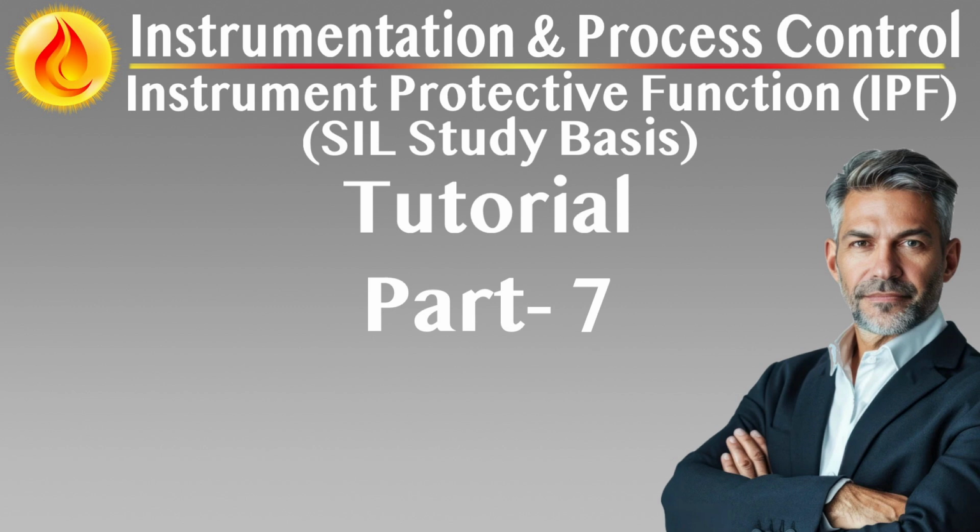Testing, validation, and maintenance requirements. Routine proof testing. All detectors must be tested at intervals defined by risk analysis and manufacturer recommendations to ensure sensor sensitivity and system response remain within specification. Testing must verify the entire loop, from detection through logic and final element.